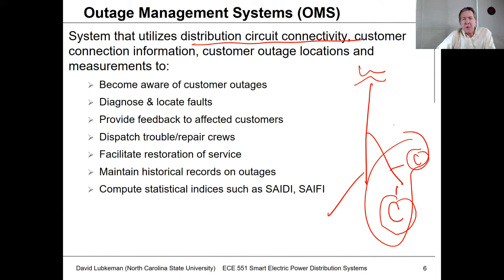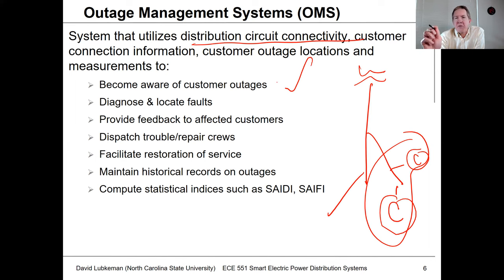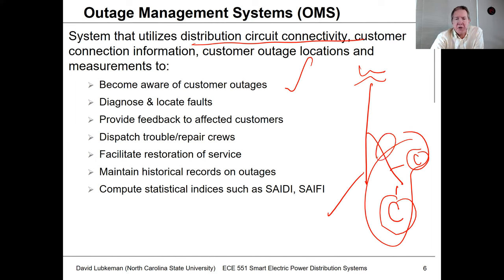What the outage management system does first is help you become aware of where outages are likely located and what's causing them. If a number of customers call in, you can trace this to a fuse, recloser, or whatever device operated. So it helps you diagnose and locate the faults.